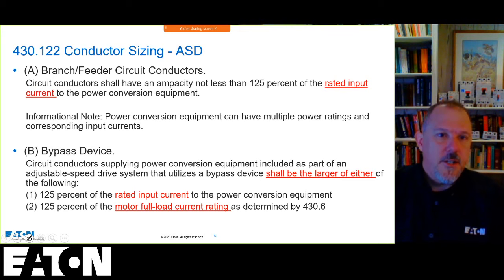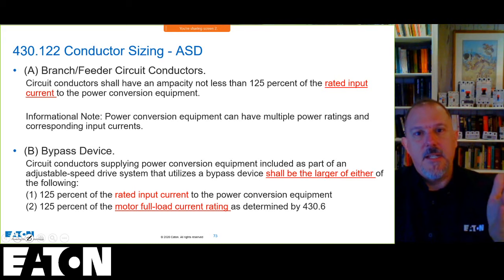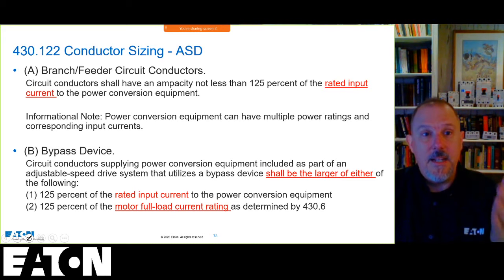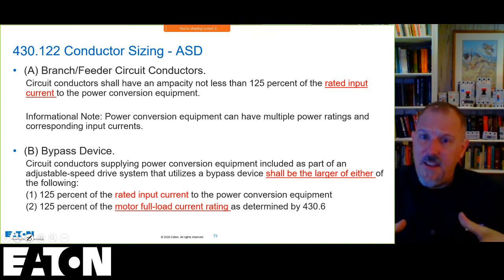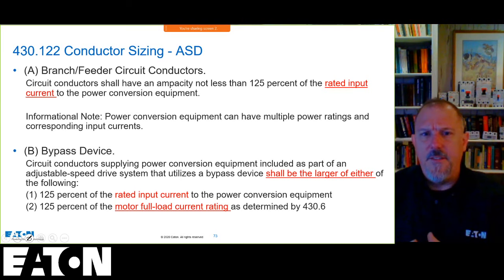So branch circuit conductors shall have an ampacity not less than 125% of the rated input current to the power conversion equipment. This is in 430.122 for adjustable speed drives.